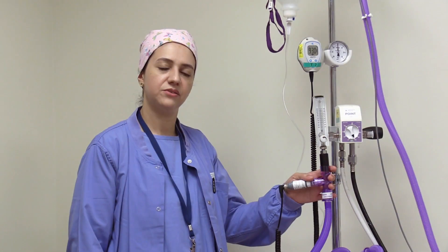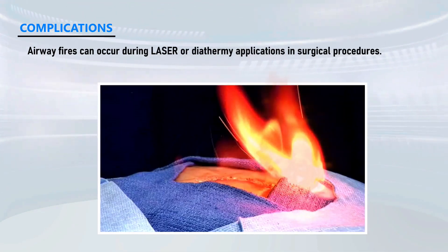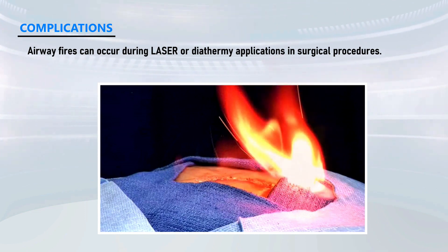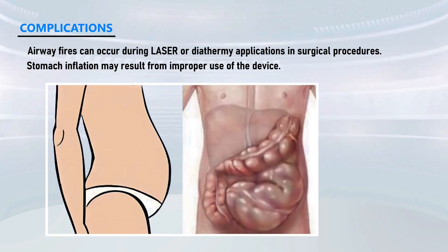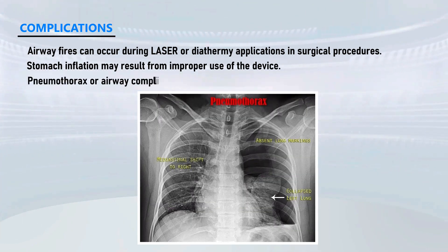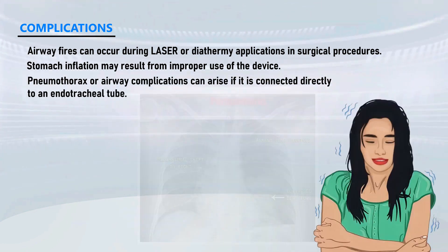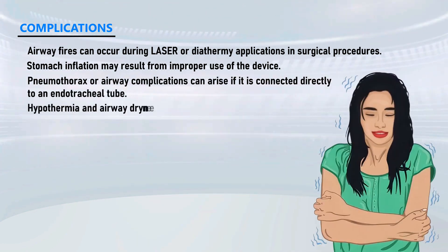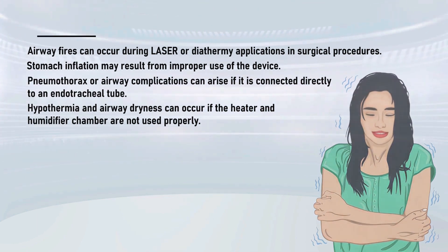Regarding complications: airway fires can occur during laser or diathermy applications in surgical procedures. Stomach inflation may result from improper use of the device. Pneumothorax or airway complications can arise if it is connected directly to an endotracheal tube. Hypothermia and airway dryness can occur if the heater and humidifier chamber are not used properly.